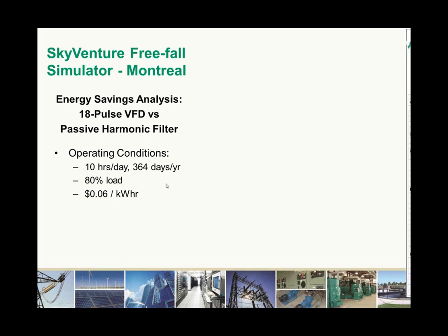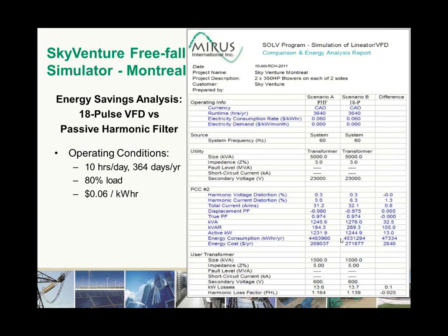So when we ran that model in our Solve software, we have a comparison report that is generated within Solve. And if we look at the comparison report, we see the reduction in energy consumption and in energy cost. 47,000 kilowatt hours per year less energy, for a savings of $2,840. So this computer simulation actually is very conservative on the energy savings. This shows a 1% energy saving. As you'll see in the next slides, the actual energy savings realized can be much more significant.